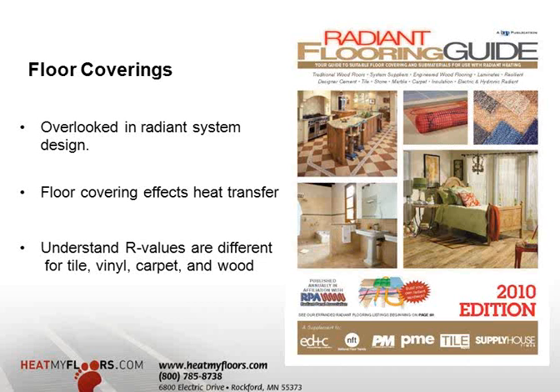Floor covering really affects heat transfer. As you get a chance looking at that radiant flooring guide, you know, obviously walking on a tile floor is cooler than walking on a carpeted floor, because their heat transfer rate through them is much different. Tile, being much cooler, is going to transfer heat right through, versus carpet. You have some insulation value there that's going to retain heat, but it's also going to take more energy to drive heat through the carpet pad and carpet.